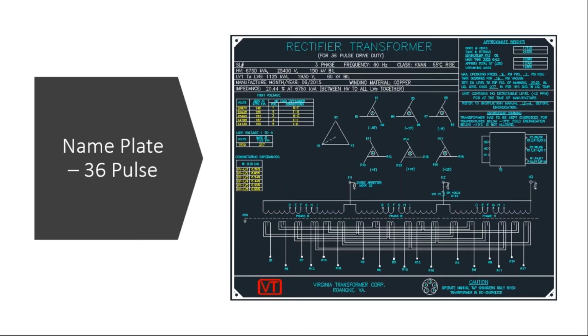The example nameplate for the same 36 pulse transformer we saw is shown here. In this case, the 36 pulse transformer needs a phase displacement of 10 degrees between the secondaries. If it is 24 pulse, it is 15 degrees, for 18 pulse it is 20 degrees, and for 12 pulse it is 30 degrees of phase displacement between the secondaries. Coming back, in this case it has 6 secondary windings, and each is displaced by 10 degrees from the next. For example, LV1 is, say, minus 25 degrees, LV2 will be minus 15, and LV3 will be minus 5.